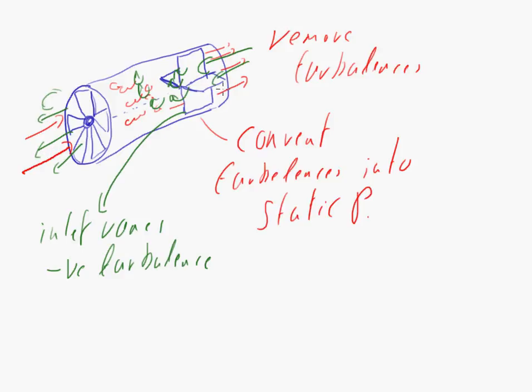Most guide vanes are outlet vanes. Inlet vanes are very rare. If you have the motor here, that's going to do a lot of turbulence. So you have the guide vanes at the inlet. Or if you have a damper mounted at the inlet creating turbulence, you want to clean up the air before it hits the impeller. Another better option is to have the guide vanes mounted alongside the motor. But in most cases, the guide vanes are on the exhaust side.